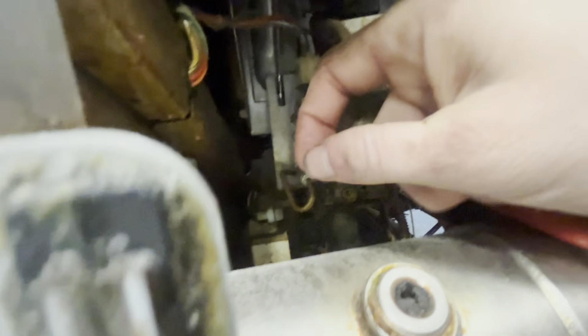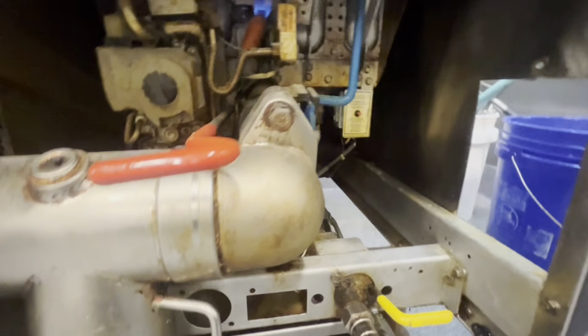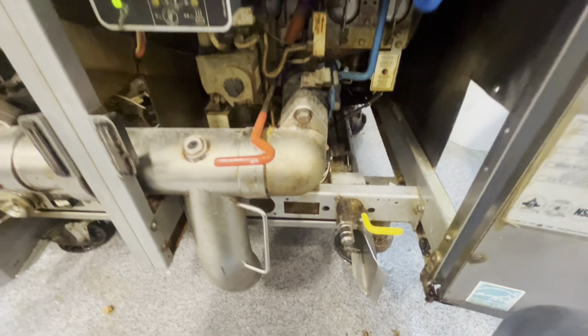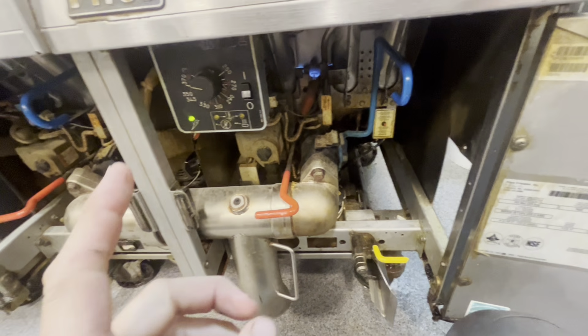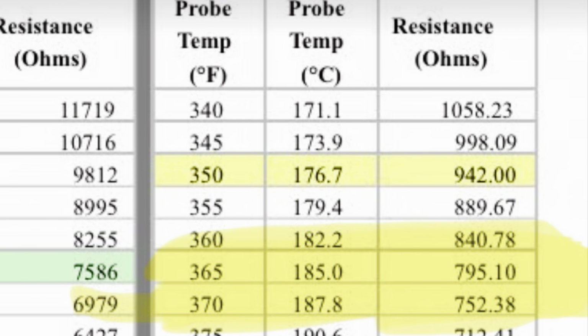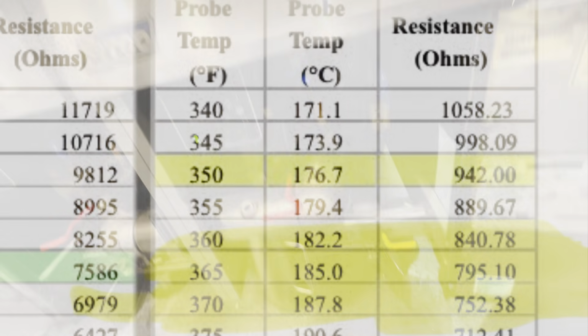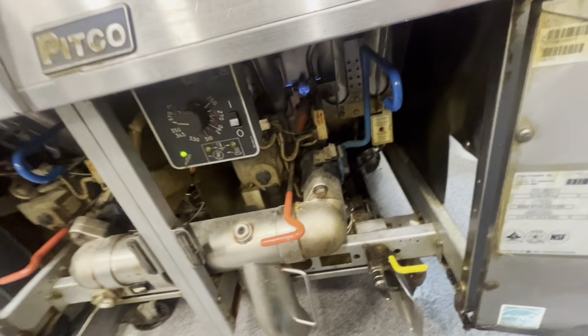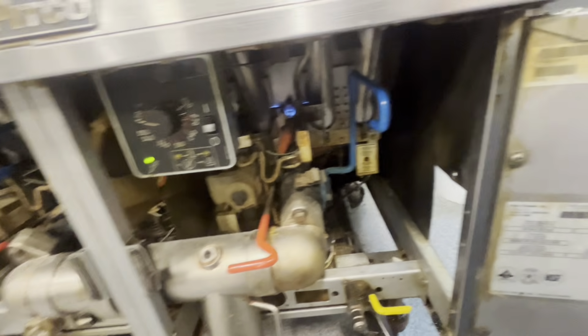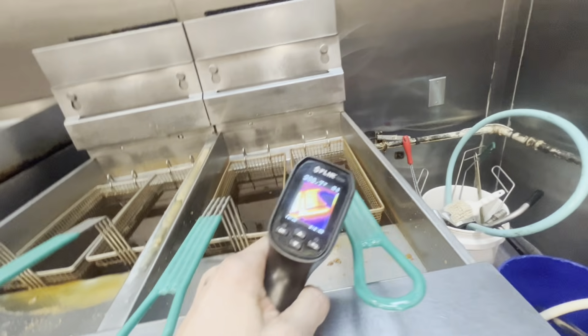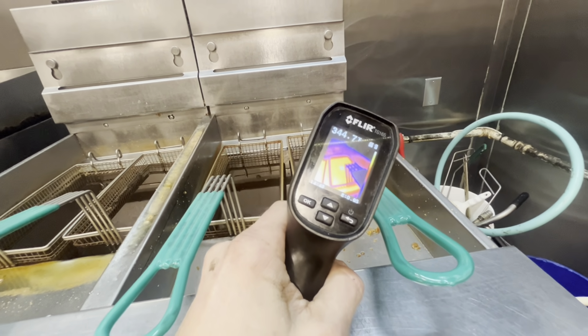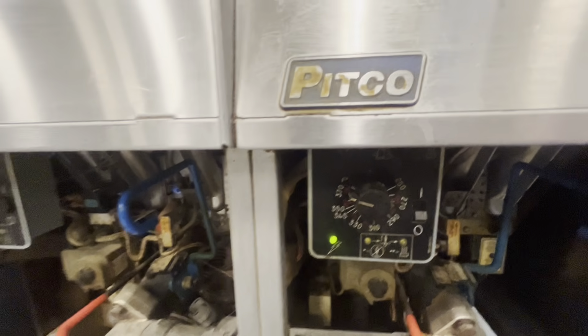I actually removed the temperature probe, which is right there. Take that and I ohmed it out, and it ohmed out at about 800 ohms. And then I ran it against this chart, which actually tells me that that temperature probe is working about spot on. It thinks it's 350. It is 350, yet I have to set this for 370.